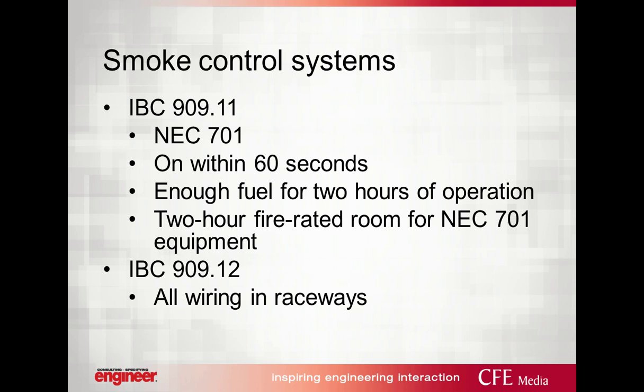Smoke control systems are going to be defined by, obviously, the size and type of the building and the occupancy. IBC 909.11 addresses it. They are connected via NEC 701, and they need to be on within 60 seconds. There has to be enough fuel for 2 hours of operation, and they need to be in a 2-hour fire-rated room per NEC 701 equipment. There is the stipulation of a sprinklered application for those rooms. The wiring for those systems, albeit they can't be cables, has to be in raceways.